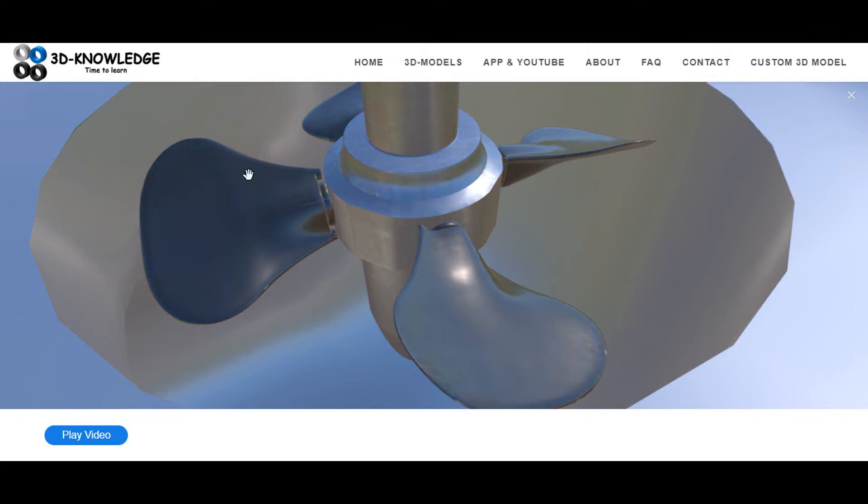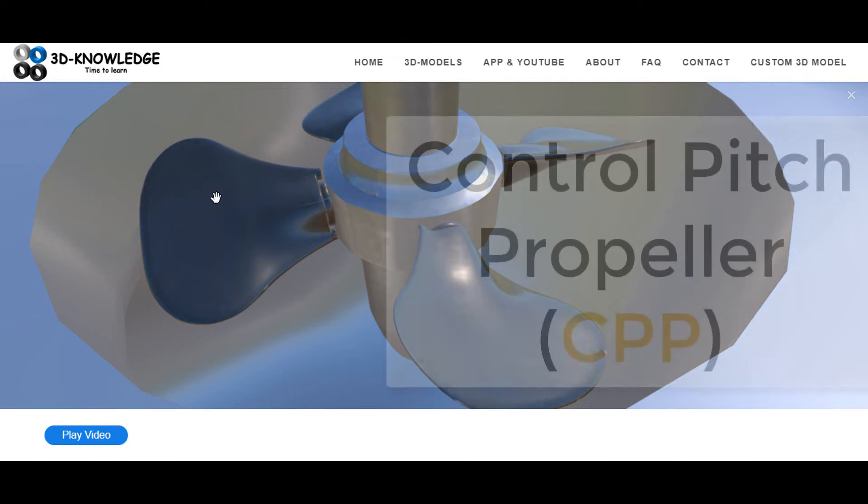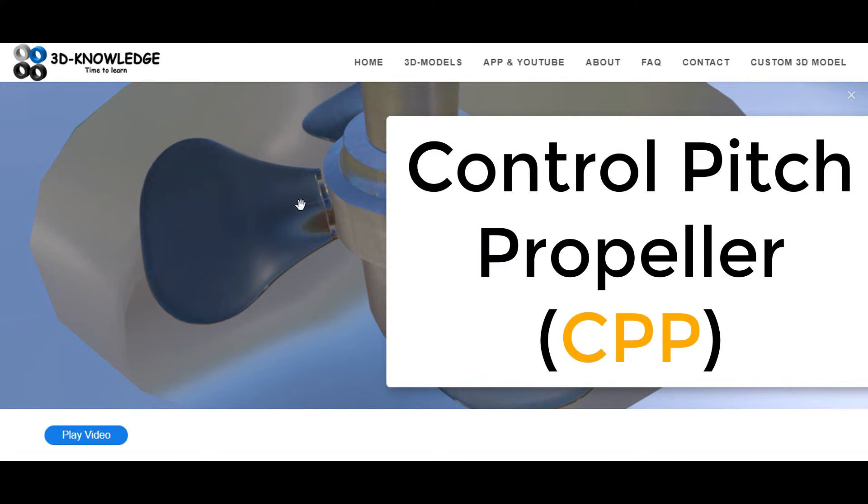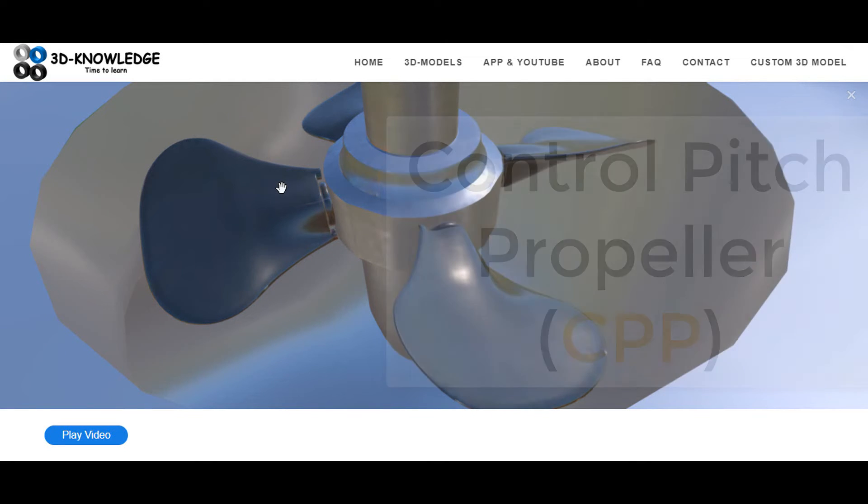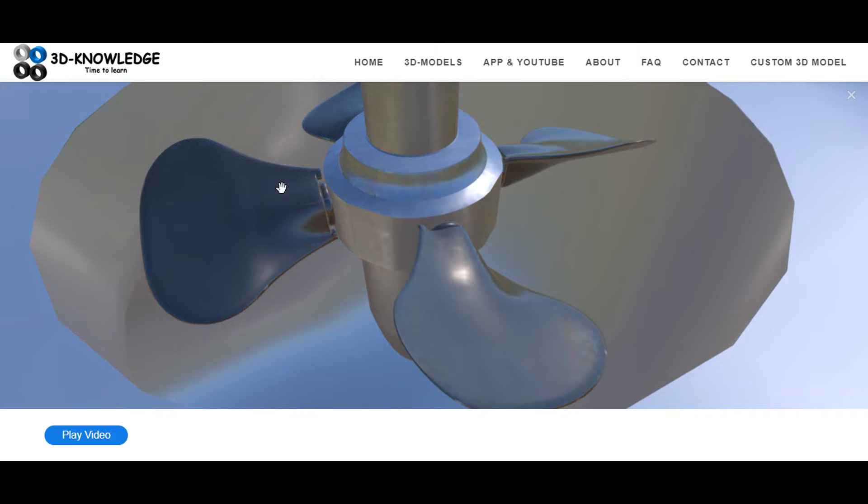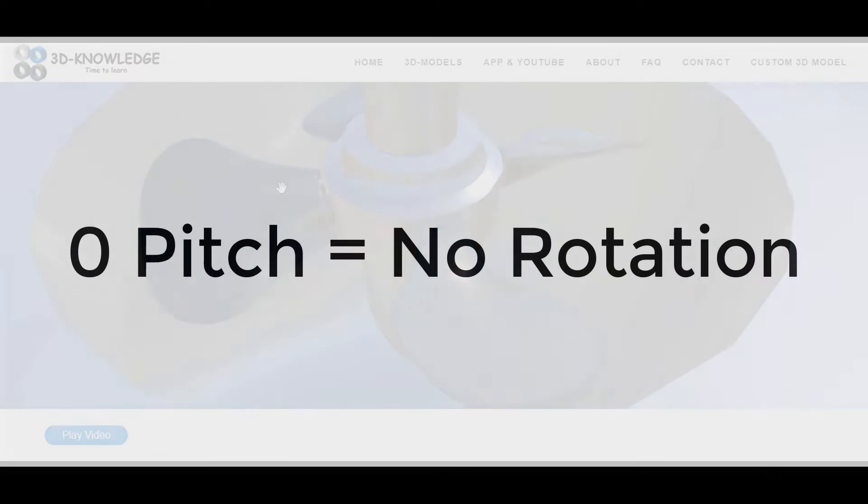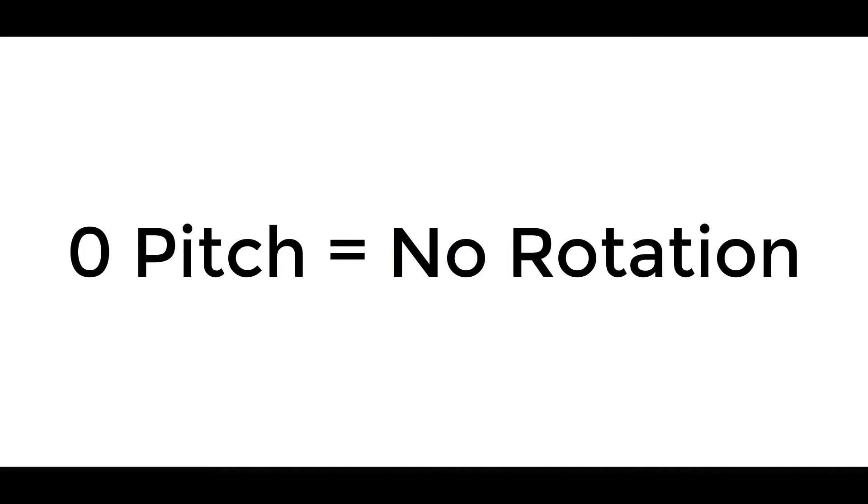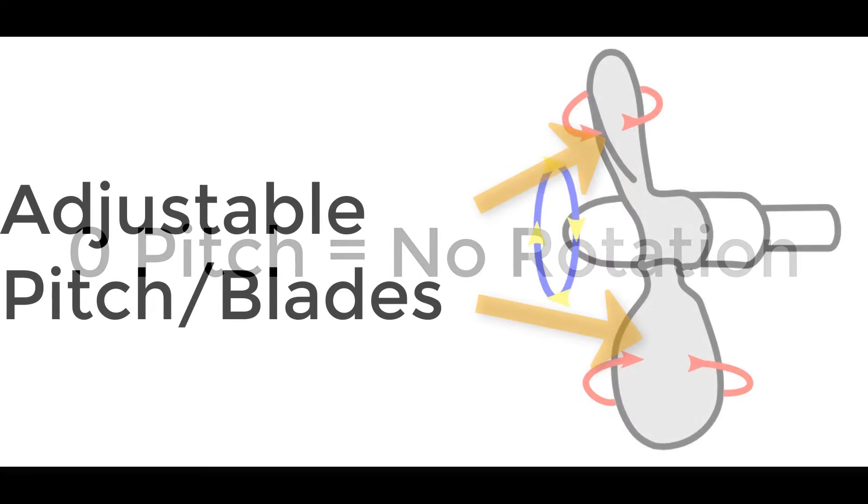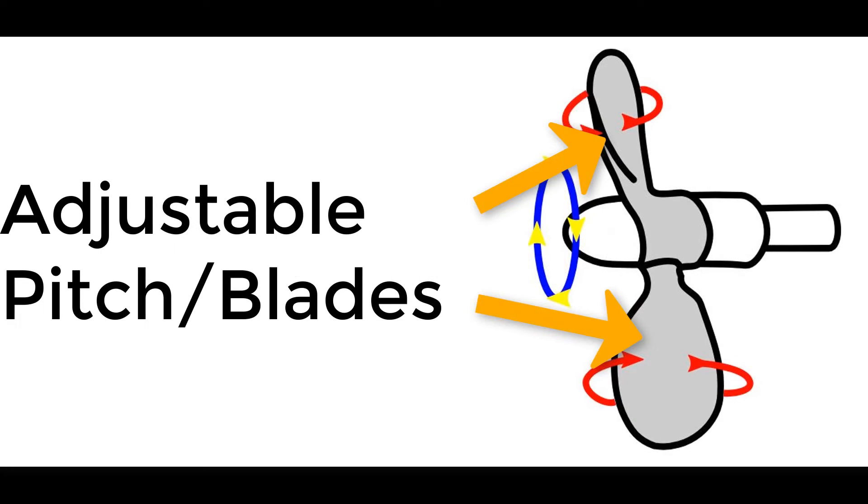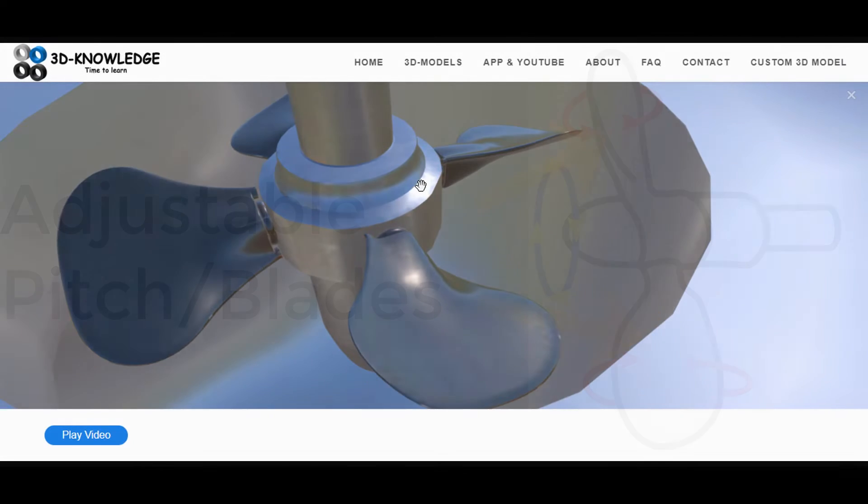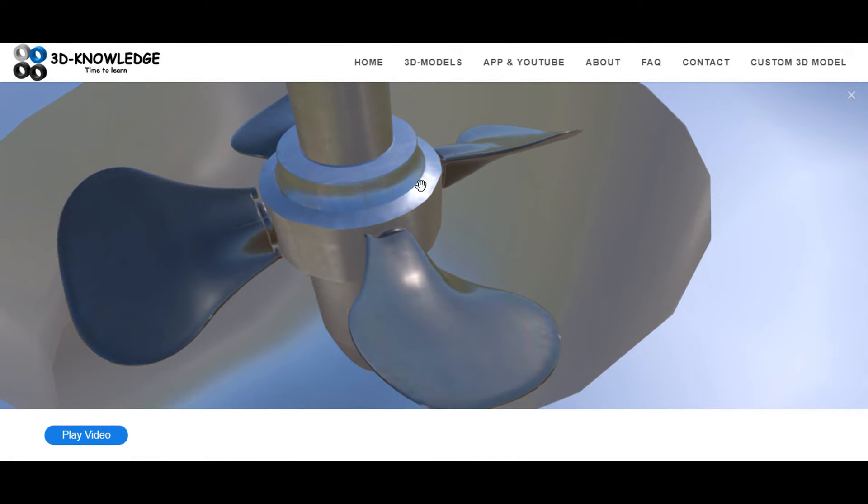The blades here are what we call CPP or controllable pitch propeller. They'll adjust and you can adjust these blades to vary the amount of power that you wish to generate. So if you turn the blades to what we call zero angle or zero pitch, then the water will just flow by and the Kaplan turbine won't rotate so it won't generate any electricity. However if we turn them to maximum pitch, we can generate the maximum amount of electricity. It's pretty useful because if the valves did fail, we could turn the blades to zero pitch and we could stop the turbine rotating. The water would continue to flow past because the valves are broken, but at least the turbine is not rotating uncontrollably.